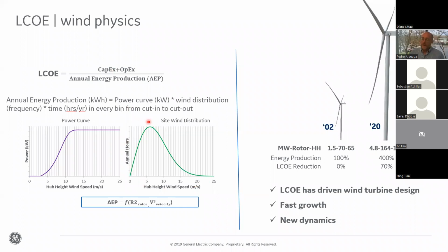The power produced by the wind is proportional to the air density, proportional to the cube of the wind speed, and proportional to the swept area of the rotor. Once you pick a site, you're really determining what the air density and wind speed are going to be like. So your ability to impact energy production really comes down to the power curve and to the rotor.